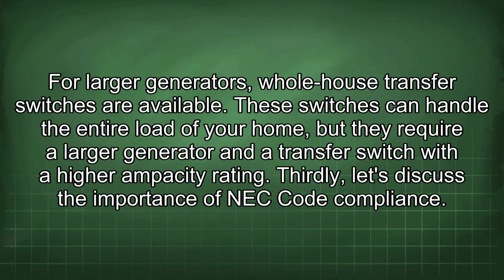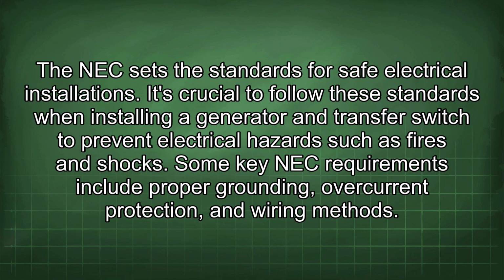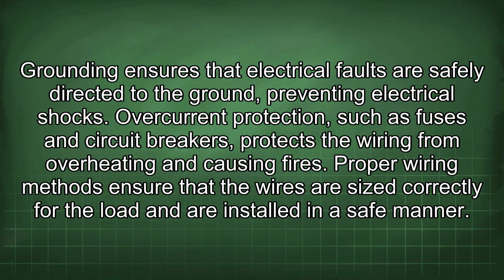Thirdly, let's discuss the importance of NEC Code compliance. The NEC sets the standards for safe electrical installations. It's crucial to follow these standards when installing a generator and transfer switch to prevent electrical hazards such as fires and shocks. Some key NEC requirements include proper grounding, overcurrent protection, and wiring methods. Grounding ensures that electrical faults are safely directed to the ground, preventing electrical shocks. Overcurrent protection, such as fuses and circuit breakers, protects the wiring from overheating and causing fires. Proper wiring methods ensure that the wires are sized correctly for the load and are installed in a safe manner.